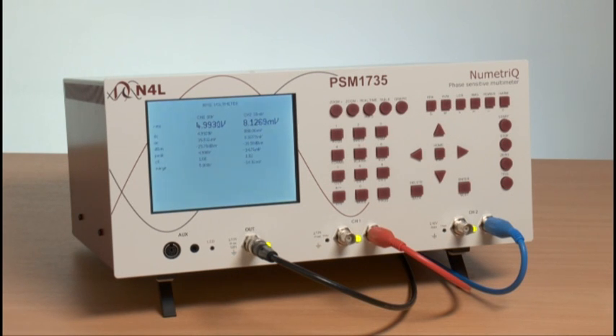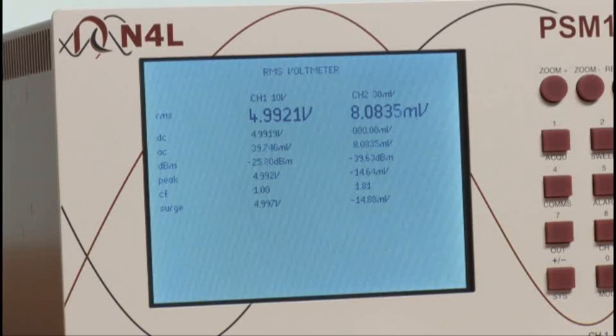The PSM 1735 is a true wideband RMS instrument, so we have AC, DC, dBm peak, crest factor, and surge measured for both channels. The channels can be voltage measurements, which is the default mode, or become current by virtue of shunts for different applications. In this case, we are just looking at voltage.